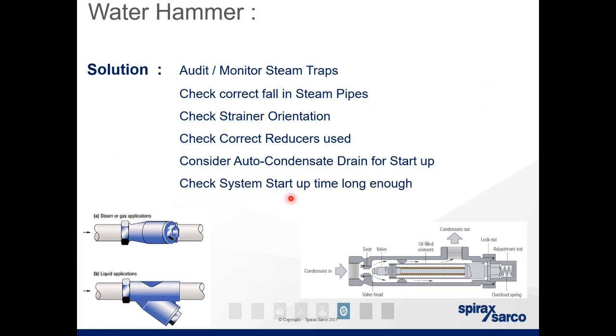And check steam startup is long enough. When we talk about these two, we're talking about when you initially start up your system, all your dirt pockets should be open as your steam is heating. As your system starts producing steam and warming up the pipes around it, you would slowly close these so that you allow the steam to build up and the condensate to be removed.